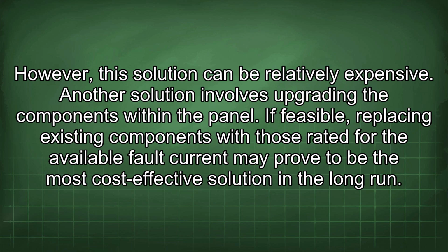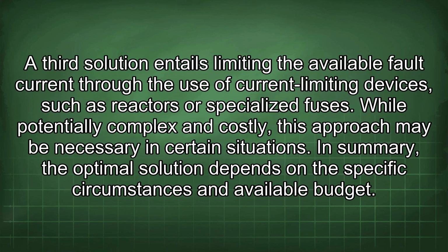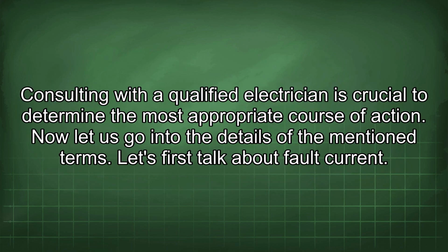Another solution involves upgrading the components within the panel. If feasible, replacing existing components with those rated for the available fault current may prove to be the most cost-effective solution in the long run. A third solution entails limiting the available fault current through the use of current-limiting devices, such as reactors or specialized fuses. While potentially complex and costly, this approach may be necessary in certain situations. In summary, the optimal solution depends on the specific circumstances and available budget. Consulting with a qualified electrician is crucial to determine the most appropriate course of action.